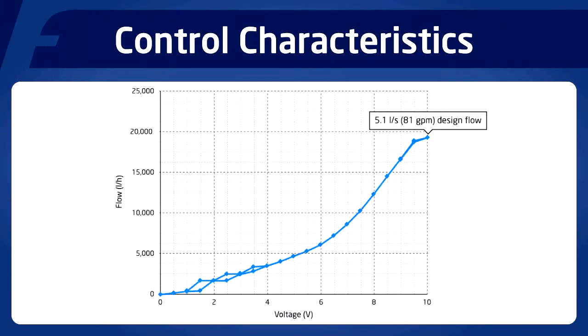With the design flow set at 5.1 litres per second, when the control signal from the actuator was received and the valve fully opened, the flow always returns to 5.1 litres per second. When the control signal is below 10 volts, the actuator changes position and modulates the flow due to the equal percentage control characteristic until tight closure when the stem is fully closed.